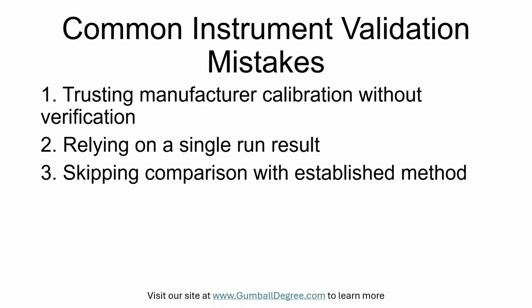A common mistake is trusting the manufacturer calibration without verifying it yourself, so always run your own standards and controls to confirm performance. Another error is assuming one successful run proves the instrument is reliable, so perform repeated measurements and document limits of detection and reproducibility to be safe.